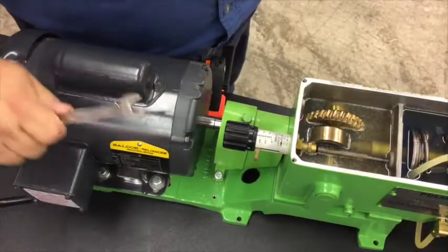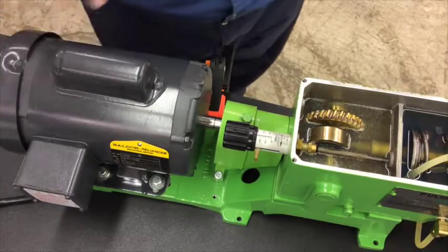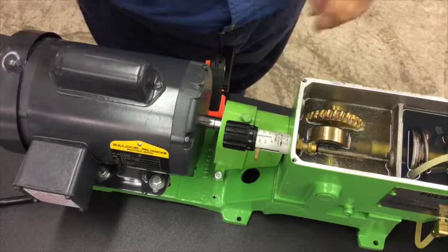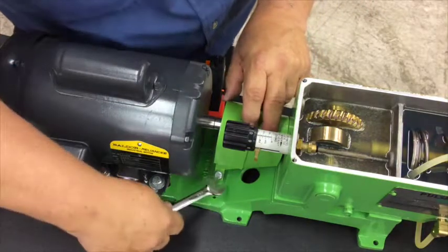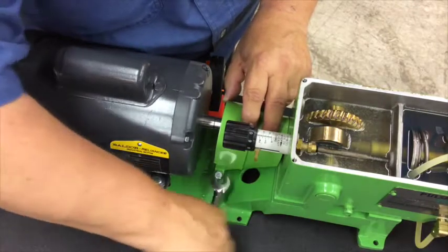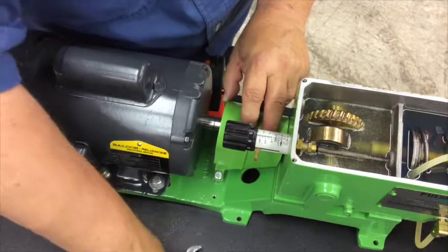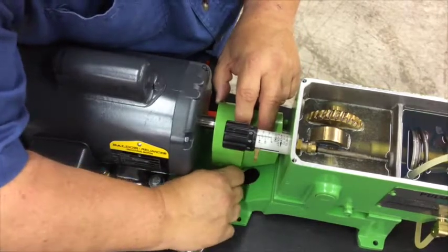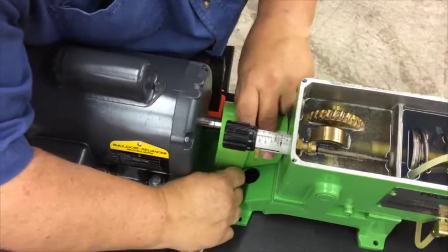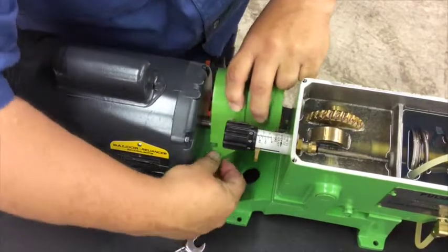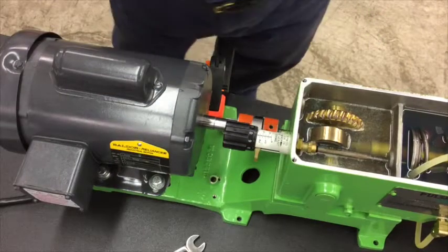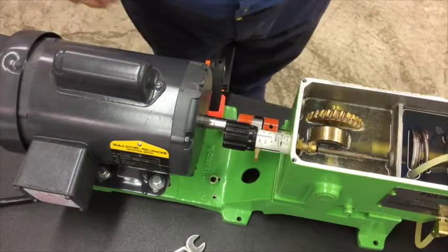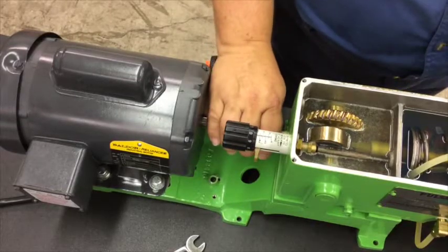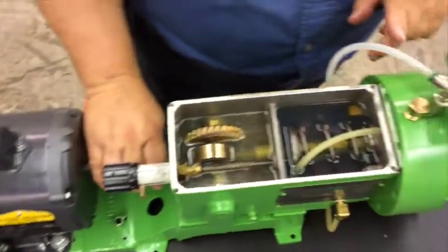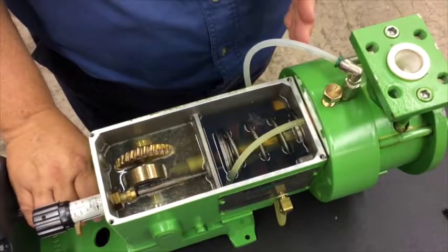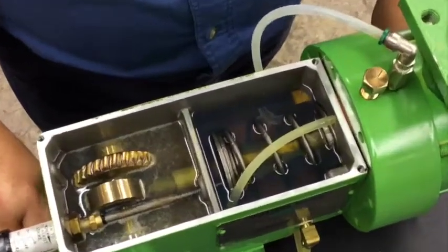We now want to remove the coupling guard so that we can manually rotate the motor shaft. This takes a 7/16 wrench, okay, and you can see that I've already loosened it. So I'll now remove it with my hand. And for the purposes of this video, I've already taken the back screw out on this side of the coupling as well. I'll set this aside. And now I want to rotate this coupling manually, and I want to make sure that the pump piston is fully retracted. So I'll start rotating it here.